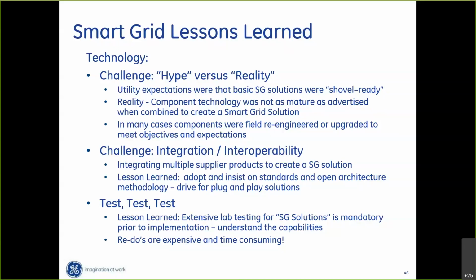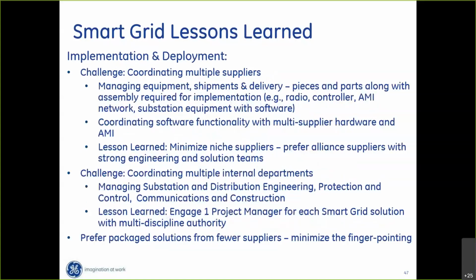Second, we learned how important standards were—integration, interoperability, compliance to the same set of standards. Third is testing: you can't test enough in the factory, and it's much easier to test there than in the field. But what we really learned was we need to do end-to-end testing, from the component in the substation up to the office and the control center. Test end to end, and coordinate multiple suppliers, because these solutions have equipment from different vendors.